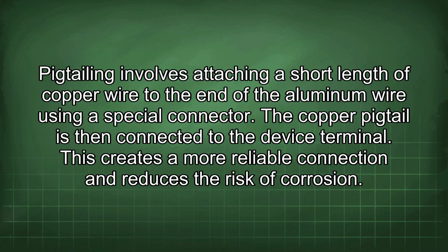Pigtailing involves attaching a short length of copper wire to the end of the aluminum wire using a special connector. The copper pigtail is then connected to the device terminal. This creates a more reliable connection and reduces the risk of corrosion.